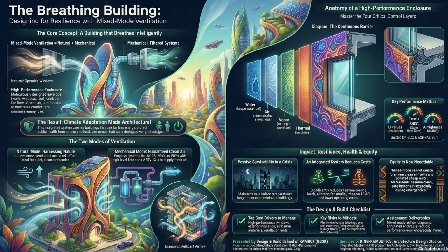So what's the mandate here? What are the architectural decisions you have to make to ensure there's parity? The mandate is crystal clear. All residents deserve clean, safe indoor air, especially during emergencies. You cannot build a two-tiered system of premium clean air units versus polluted but cheaper units. So how do you avoid that? To ensure parity, the designer has to invest in specific mitigation measures for that less desirable side. Like what? It means investing in specialized acoustic attenuation. That means thicker glass, more complex window framing, noise-dampening facade layers on the street side, so that when the windows are open, the noise is minimized. It also means ensuring that the mechanical system, the DOAS and the HRV, delivers the exact same high standard of filtered air, say MERV 13 filtration, to every single unit, no matter which way it faces.